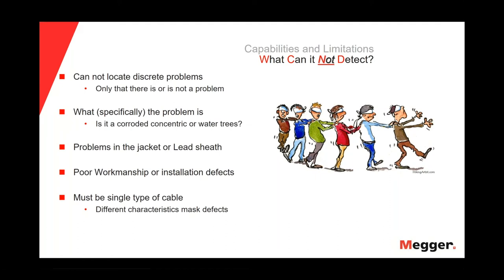Also, we cannot see problems in the jacket or the lead sheath, and of course, we cannot see poor workmanship or installation defects. And we should use the tan delta on a single type of cable, because if we have mixed cable, different characteristics will mask the defects.